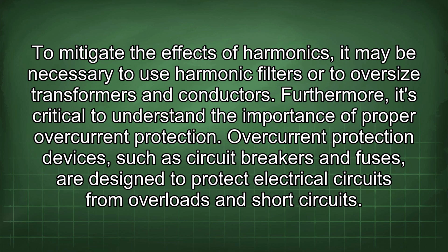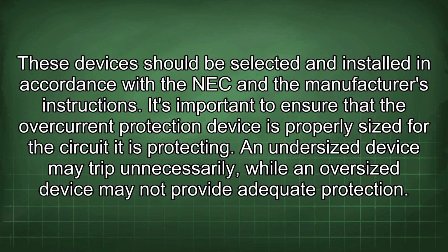Furthermore, it's critical to understand the importance of proper overcurrent protection. Overcurrent protection devices, such as circuit breakers and fuses, are designed to protect electrical circuits from overloads and short circuits. These devices should be selected and installed in accordance with the NEC and the manufacturer's instructions. It's important to ensure that the overcurrent protection device is properly sized for the circuit it is protecting. An undersized device may trip unnecessarily, while an oversized device may not provide adequate protection.